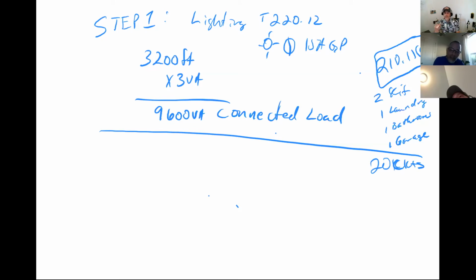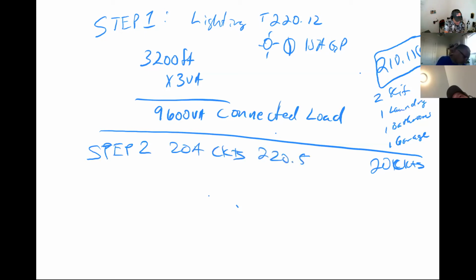We don't care about them for the load calculation for the feeders, so it's only the kitchen appliances and the laundry. There's 3 of the 5 that we actually have a number for at this point. So step 2 is the required 20-amp circuits that have a load calculation in 220.52, and that's 1500 times 3, because I've got 2 in the kitchen, 1 laundry.